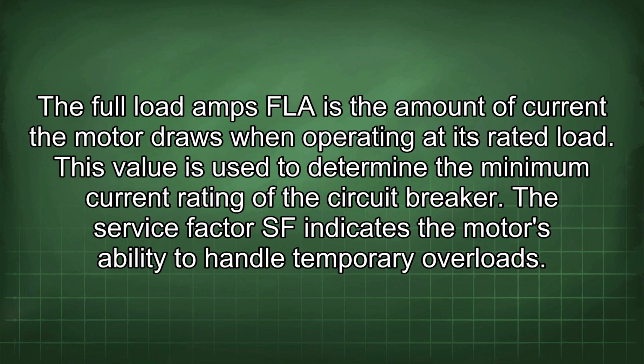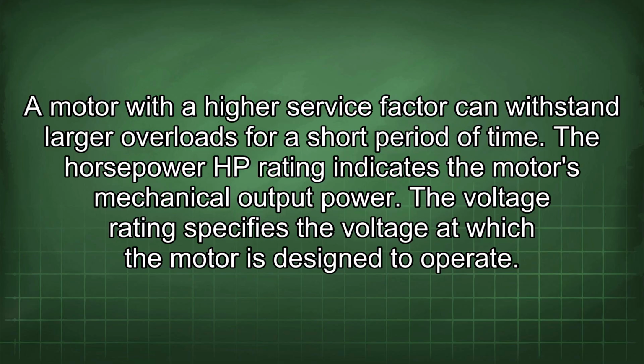The full load amps (FLA) is the amount of current the motor draws when operating at its rated load. This value is used to determine the minimum current rating of the circuit breaker. The service factor (SF) indicates the motor's ability to handle temporary overloads. A motor with a higher service factor can withstand larger overloads for a short period of time. The horsepower (HP) rating indicates the motor's mechanical output power. The voltage rating specifies the voltage at which the motor is designed to operate.